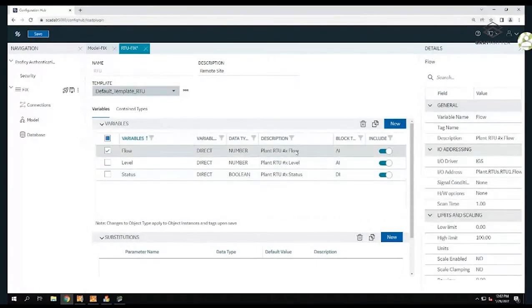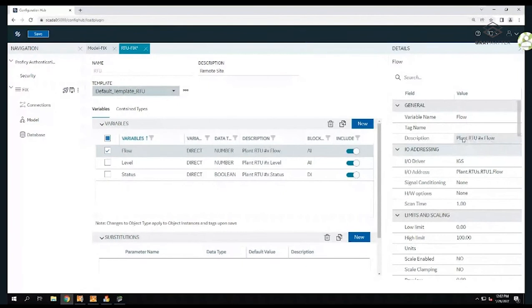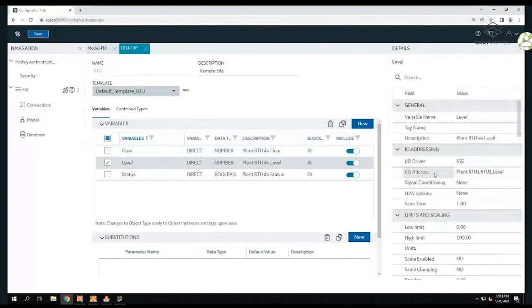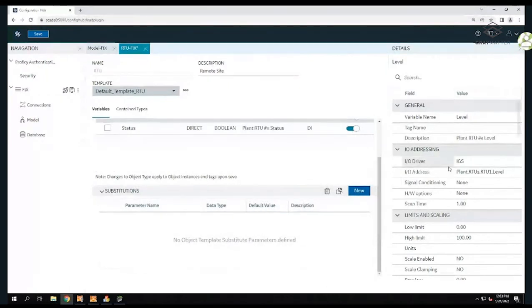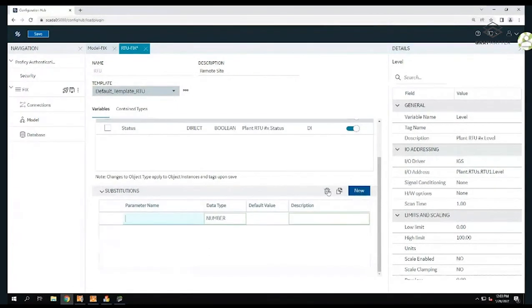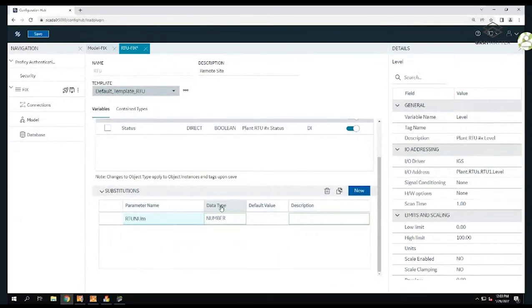You'll notice on the right side, as I go in, it's changing the description - there's the IO address that came from RTU number one, and there's my generic placeholder. These are my tag names familiar in iFIX with the same different fields. I'd like to do a substitution - instead of hard-coding names or addresses, I'm going to substitute these dynamically based on each RTU instance. I'll add a couple substitutions: I'll call it RTU number, value one. This is like your PID number - loop 101 or loop 201.